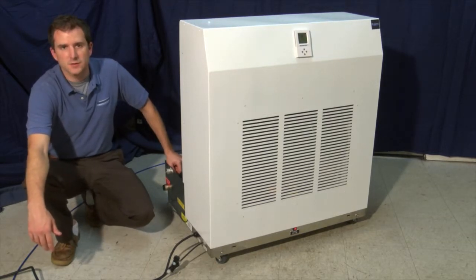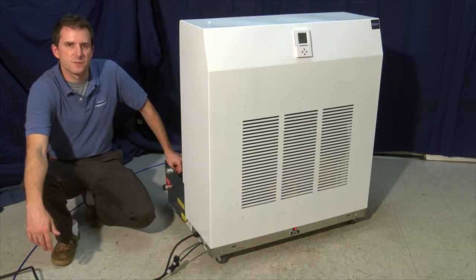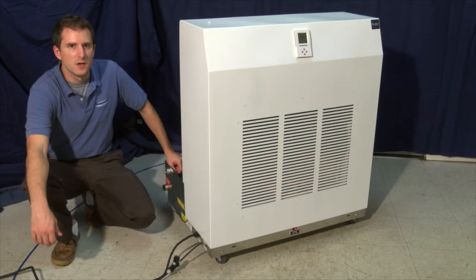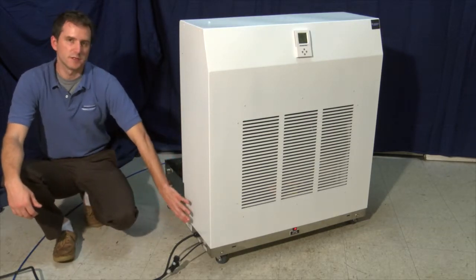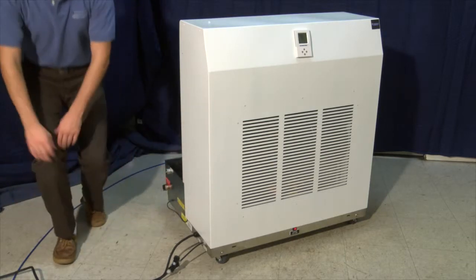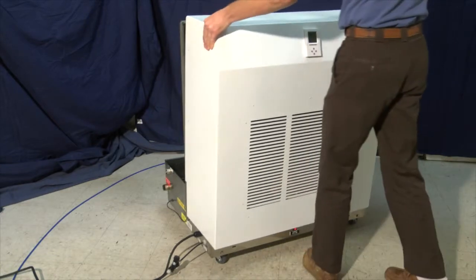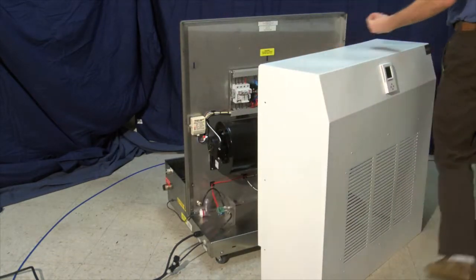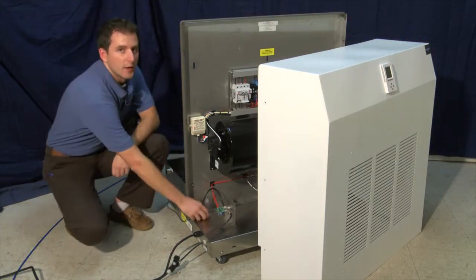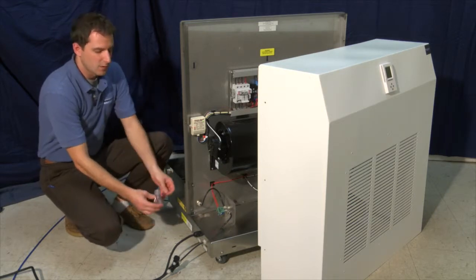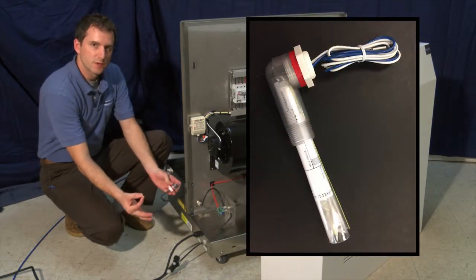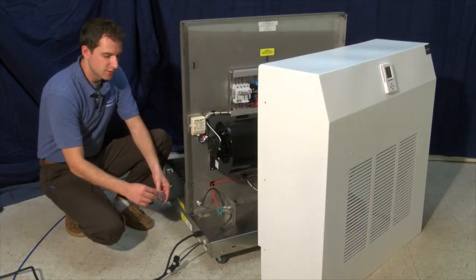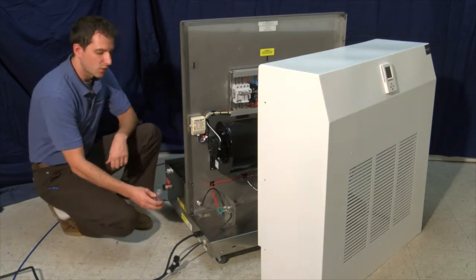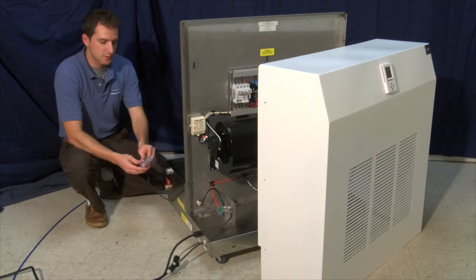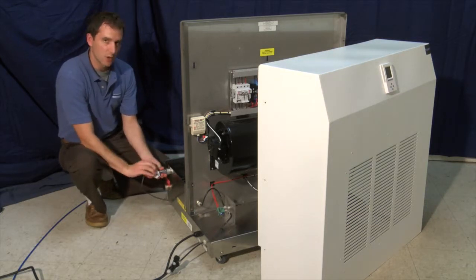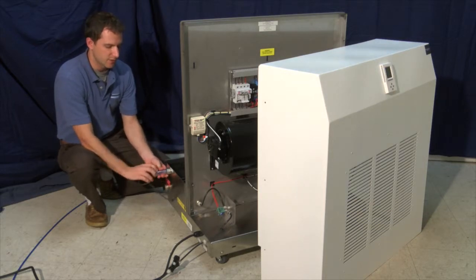The water guard is an optional overflow detection system used to protect your mist-free humidifier and the area around it during an overflow. A new mist-free will have the water guard sensor inside the fan cover to protect it during shipping. To install, remove the fan cover as discussed earlier and locate the water guard sensor tube. Note, there will be a small bag of rock salt inside the tube during shipping. This is inserted in the tube to create conductivity for treated water. Insert the salt into the tube and screw onto the overflow pipe connection on the side of the mist-free.